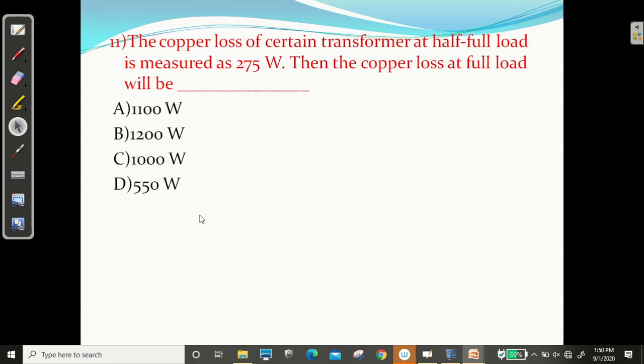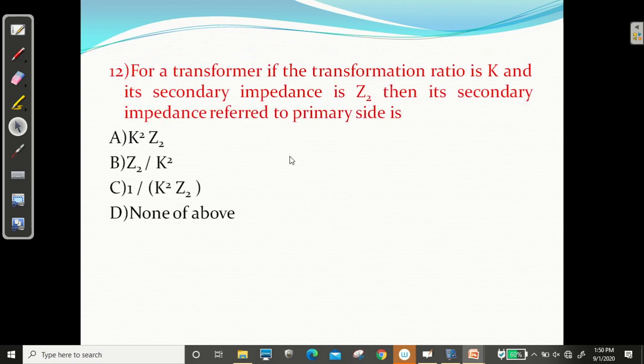11. Copper loss of a certain transformer at half full load is measured as 275 watt. Then the copper loss at full load, same question, at full load it will be double squared: 275 plus 275 plus 275 plus 275, that is 1100 watt. This answer is correct.